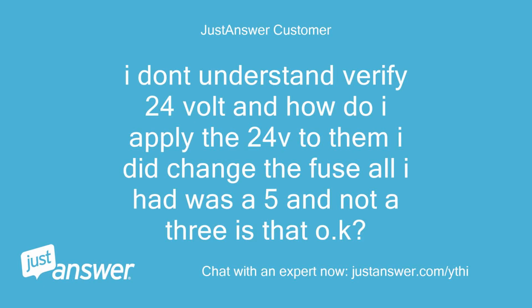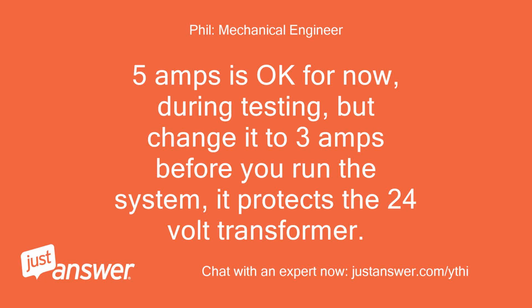I don't understand. Verify 24 volt, and how do I apply the 24V to them? I did change the fuse. All I had was a 5 and not a 3. Is that okay? 5 amps is okay for now, during testing, but change it to 3 amps before you run the system. It protects the 24-volt transformer.